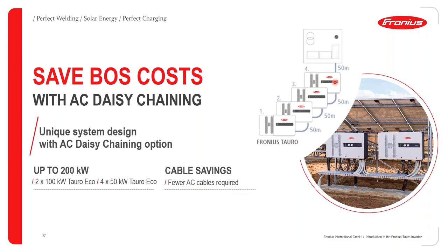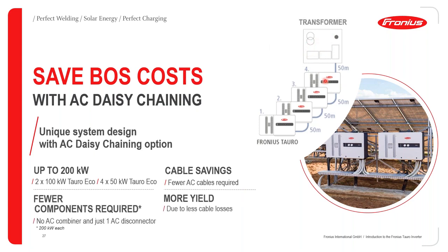So the normal configuration would look like this. You have your transformer at the very end here, and then all the inverters. From the transformer to the first inverter is a distance of about 50 meters. And then from the first inverter to the last inverter, using the 50 kilowatt versions, you have them spaced 50 meters apart. If you do not have the daisy chaining capability, every inverter, or every 2 inverters, would have to go through an AC combiner box. And therefore the cost of your balance of system, as far as the combiner boxes is concerned, would double.